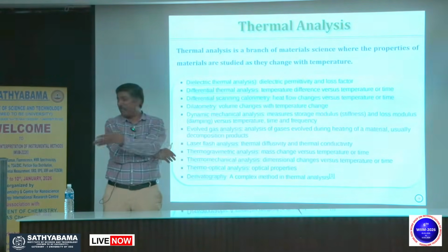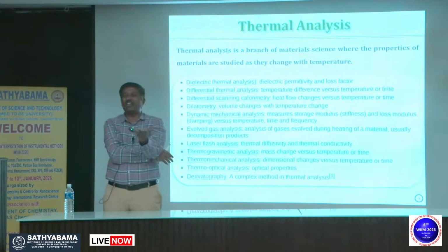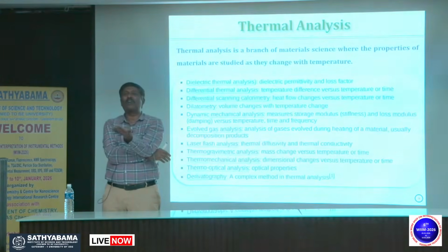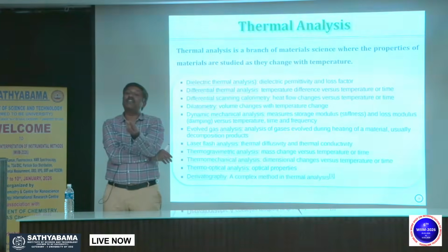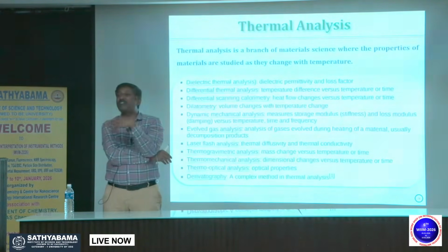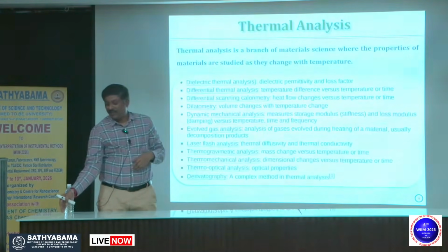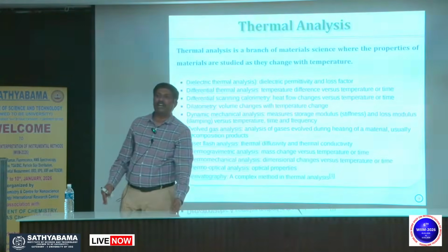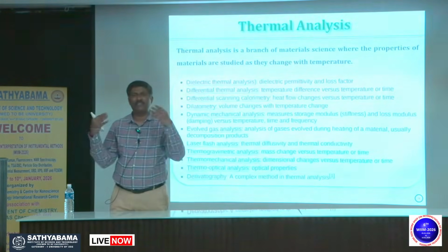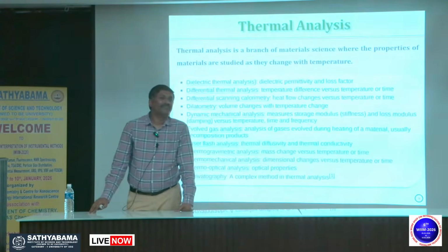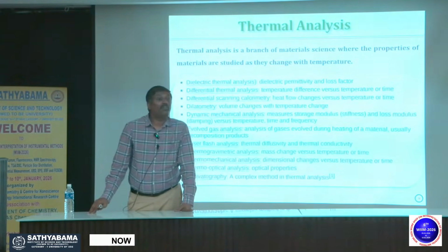We say standard. A thermometer, when we say graduated, a certificate will be there, no? In India, we have what is called ISI. That certificate, NIST, that certificate cost is very high. You have a non-certified thermometer and a certified thermometer. Exactly the same working principle, same thing. Cost would be maybe 10 times different. Because somebody checked.